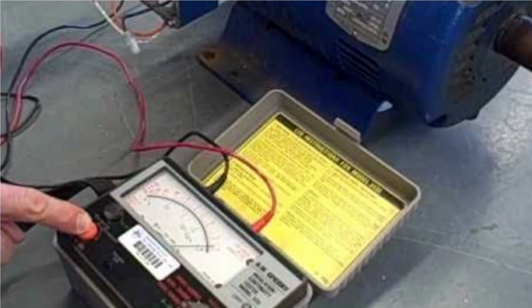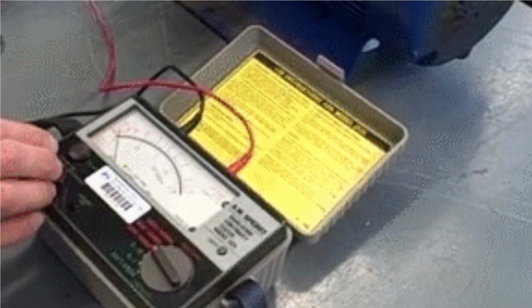Since the strength of the insulation varies with temperature and humidity, you may need to perform several measurements of the resistance over some time to get a consistent result. Place one Megger lead on the ground terminal or wire and place the other lead on one of the phase wires or terminals. Press test on the Megger.